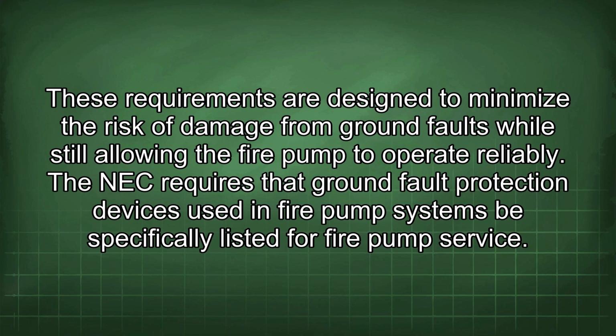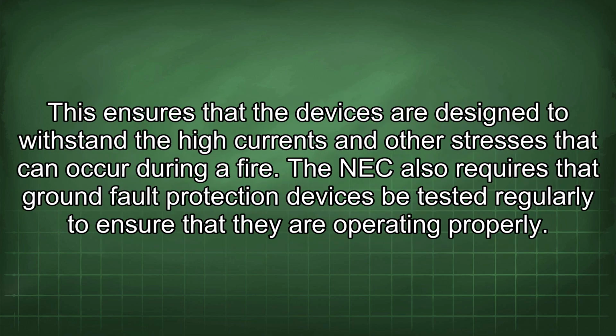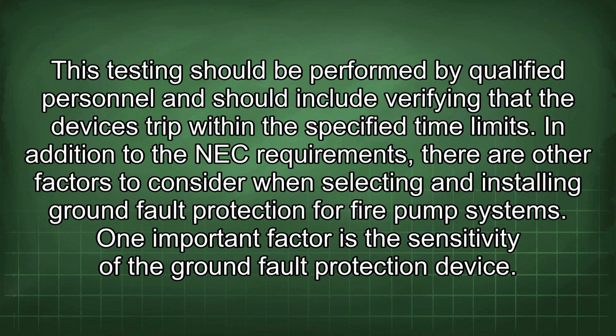The NEC requires that ground fault protection devices used in fire pump systems be specifically listed for fire pump service. This ensures that the devices are designed to withstand the high currents and other stresses that can occur during a fire. The NEC also requires that ground fault protection devices be tested regularly to ensure that they are operating properly. This testing should be performed by qualified personnel and should include verifying that the devices trip within the specified time limits.